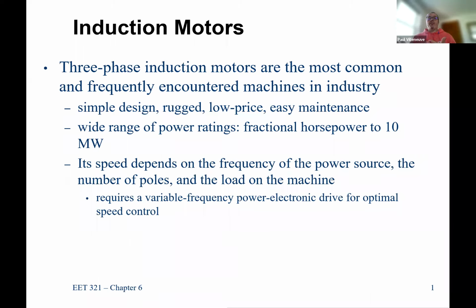So in a variable frequency drive, you can go ahead and just vary that value, that frequency or that speed, and then you can accurately control the water levels, whatever you're trying to control. So variable frequency drives are far more efficient because a recirc line basically says, take water that you pumped into one location and send it back to where you took it from and just recirculate it. Not very efficient. You're just kind of redoing the process.